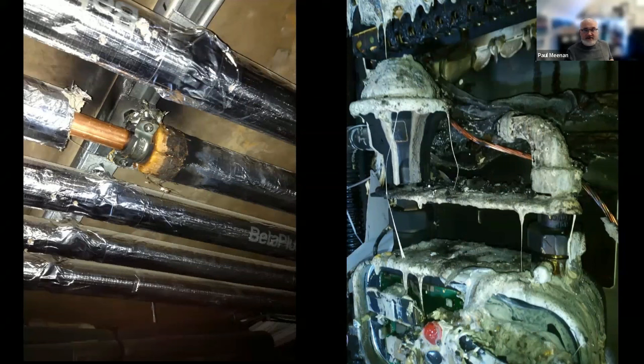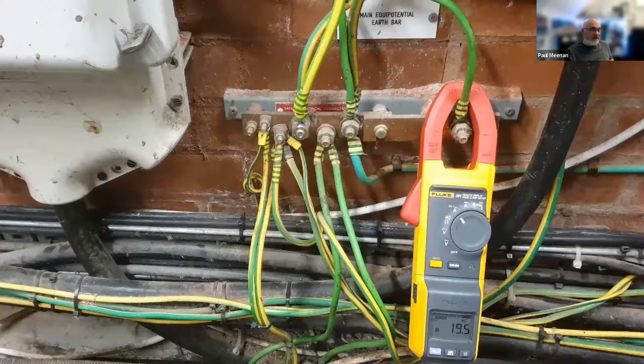On the right, there's a gas meter that's melted through a fire caused by the sheer level of energy that was pumped through it, and also insulated pipework where the insulation got so hot it melted and fell off. And that's on pipes you don't expect to be carrying electricity. So in England, we don't get it right, and there is a reason behind that.